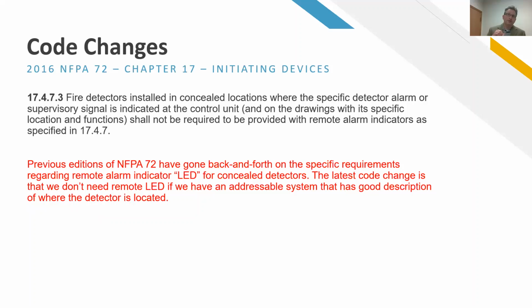Here's a new section that the code's gone back and forth on. This has to do with concealed detectors, detectors you cannot see. Generally, it's going to be your duct smoke detectors, which would be for an air handling unit, generally on the return side, or poked into a duct that's detecting smoke at a fire smoke damper. If you can't see them, the code used to require you have a remote LED, like the size of a single gang plate, like a light switch. You have an LED on it so you can identify the location.